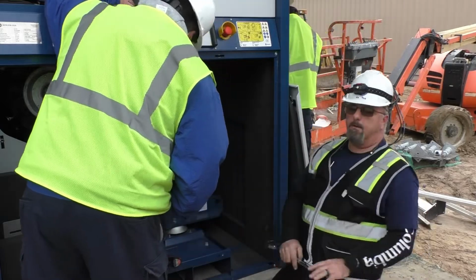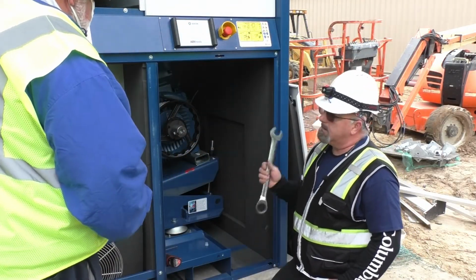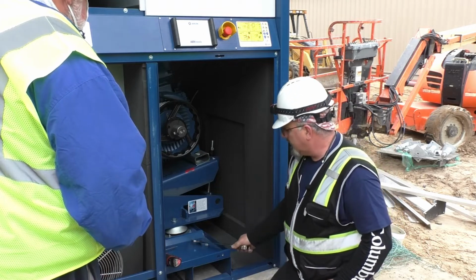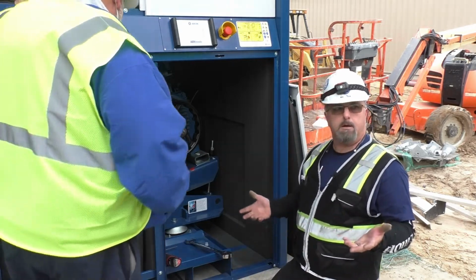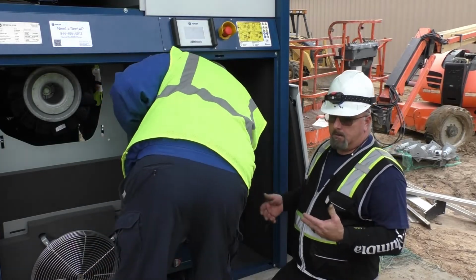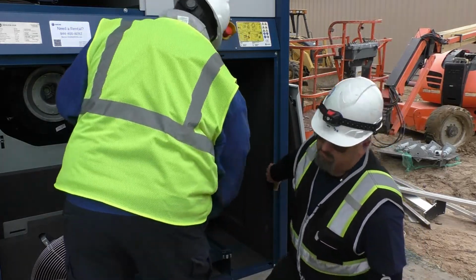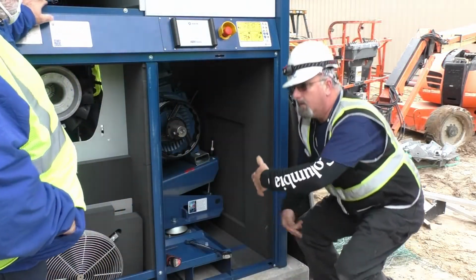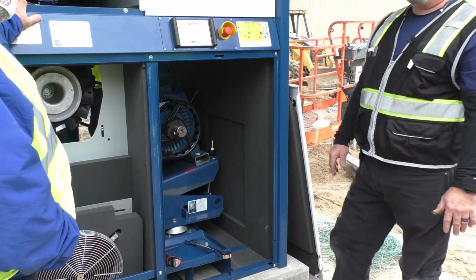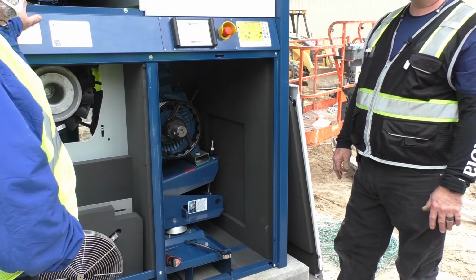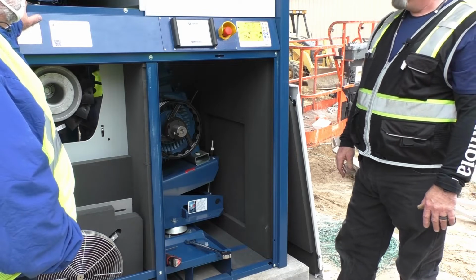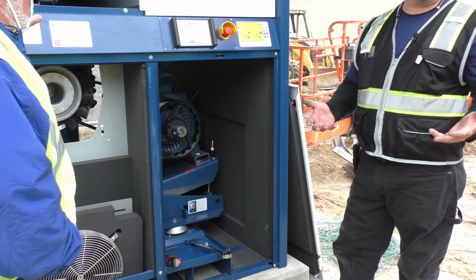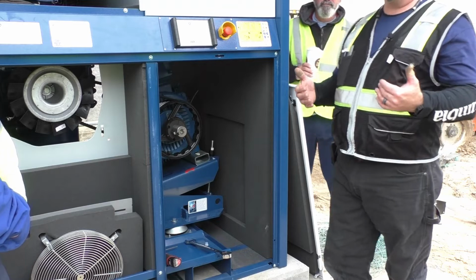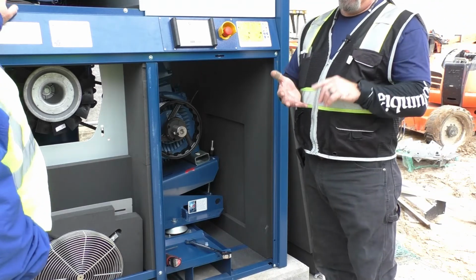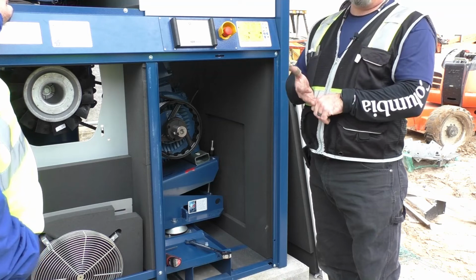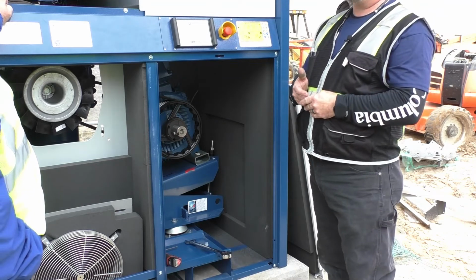Now for doing alignments on the unit, it should be checked once a year. Now, like I said, for me, I have a laser tool called a belt hog for doing belt drive alignments. We do sell those if y'all are interested and you have enough belt drives to be able to justify the cost, because they do run, I think it's $1,600 or $2,600. I can't remember which. But it is a complete kit, and it's not just for one particular size belt drive. But like I said, it is a laser alignment tool for belt drives. It saves you time, and if you follow the instructions, it pretty much guarantees a proper alignment.